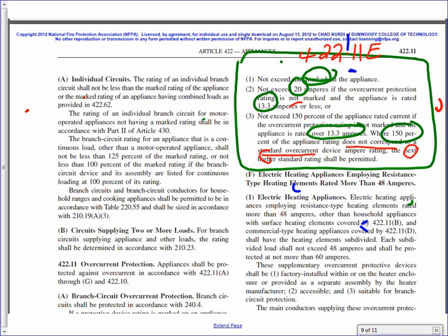And not to exceed 150% of the appliance's rated current if the appliance is rated more than 13.3 amps. And if you don't hit the standard, you can go to the next standard. One more time. If you go through this one, the cutoff is the full load amps of the appliance. Is the full load amps of the appliance 13.3 amps or less? Then the overcurrent protection device cannot be larger than 20 amps, circuit breaker. If it's more, then your multiplier is 150%. Can I have a thumbs up? Do we fully understand that one?